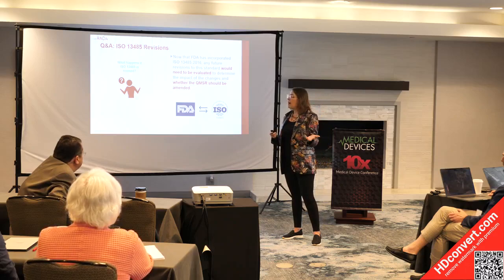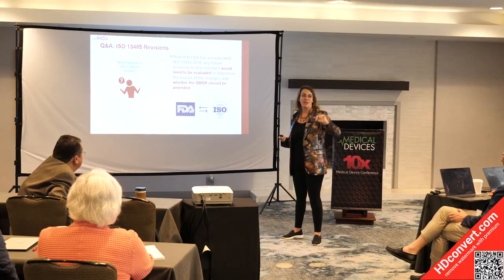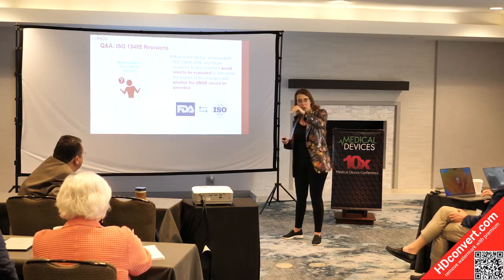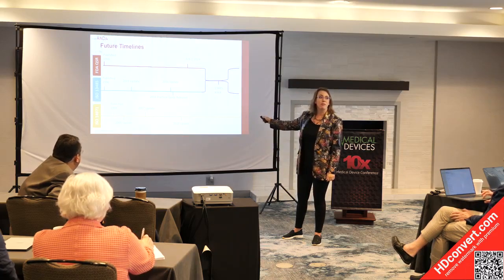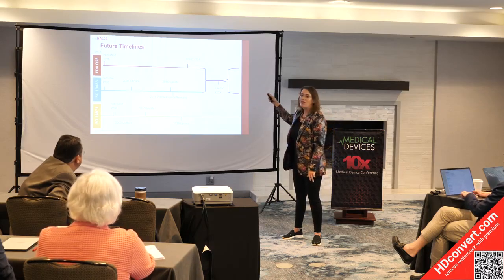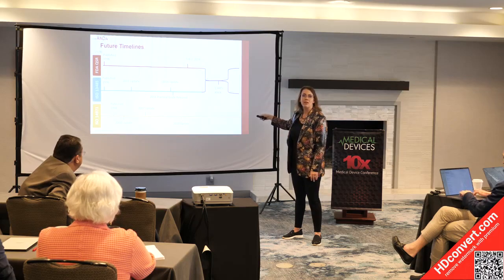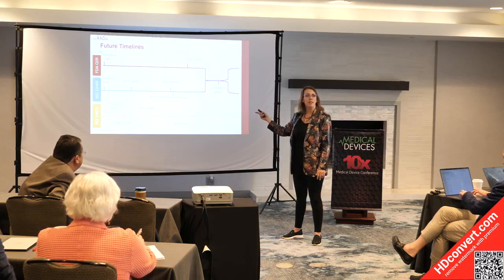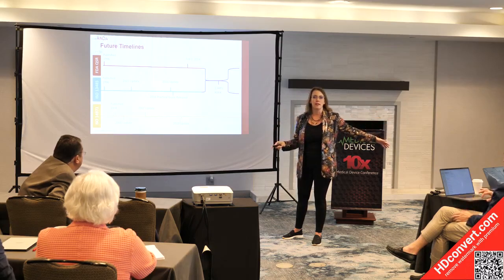What happens if ISO 13485 is revised? This is important because ISO 13485 is now a regulation in the US, not a voluntary standard. It goes up for revision every three years — it doesn't necessarily get revised, but it could. Just as long as it took to harmonize, we could de-harmonize just as fast if changes are made that require FDA to go through the whole regulatory process again — a process that has been ongoing since 1996.